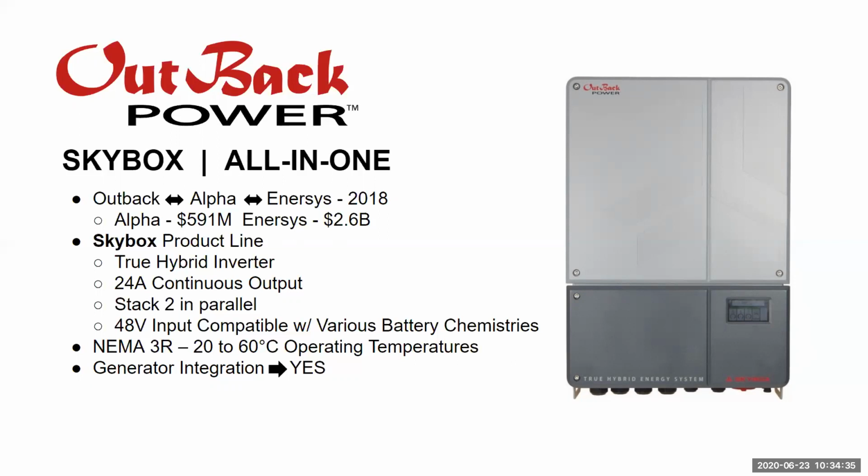This is a low voltage solution, so you can pair any 48 volt battery with it. If you want to do lithium, great. If you want to do flooded, great. You can just set your battery voltage set points in your configuration when you're commissioning, and everything will work as long as you know the parameters that your battery is operating under.